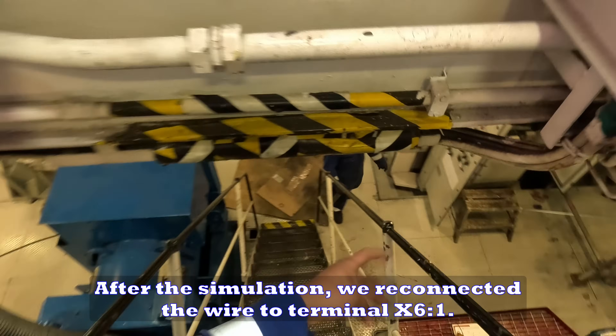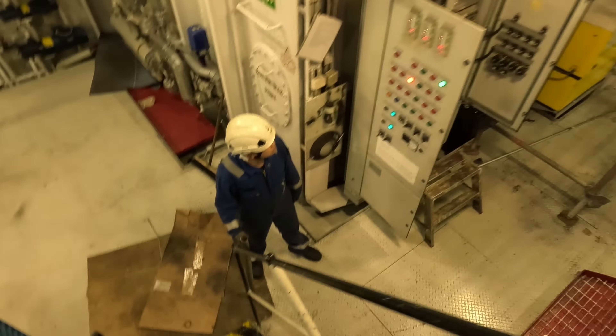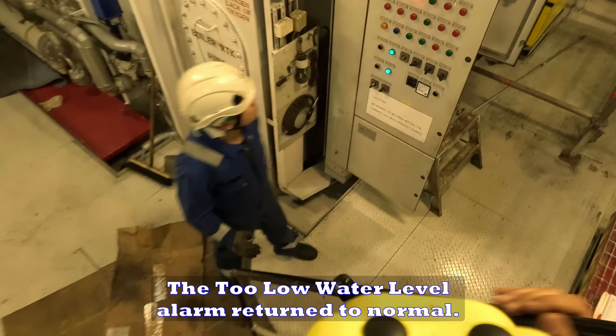After the simulation, we reconnected the wire to terminal X61. The Too Low Water Level alarm returned to normal.